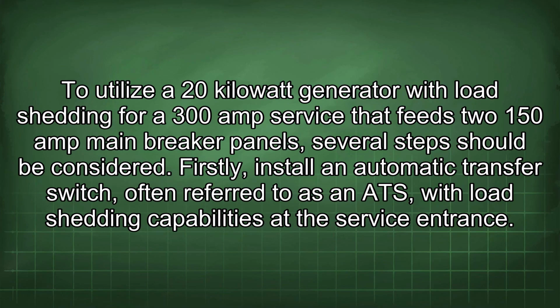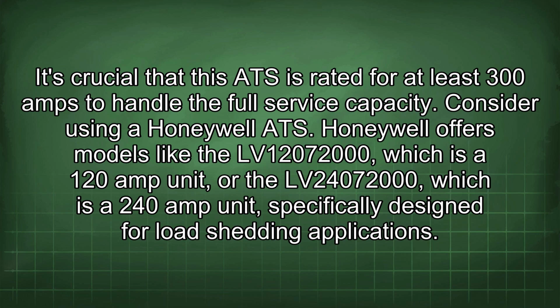To utilize a 20 kilowatt generator with load shedding for a 300 amp service that feeds two 150 amp main breaker panels, several steps should be considered. Firstly, install an automatic transfer switch, often referred to as an ATS, with load shedding capabilities at the service entrance. It's crucial that this ATS is rated for at least 300 amps to handle the full service capacity.